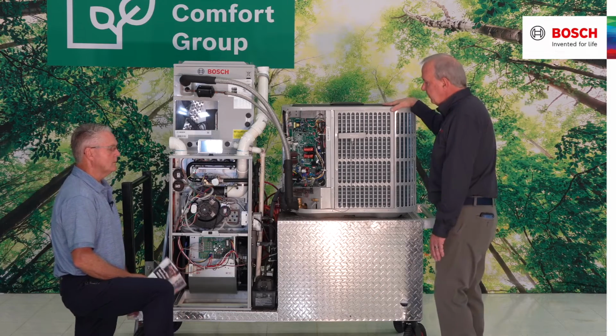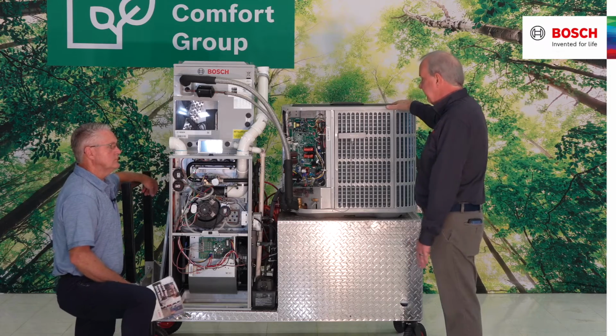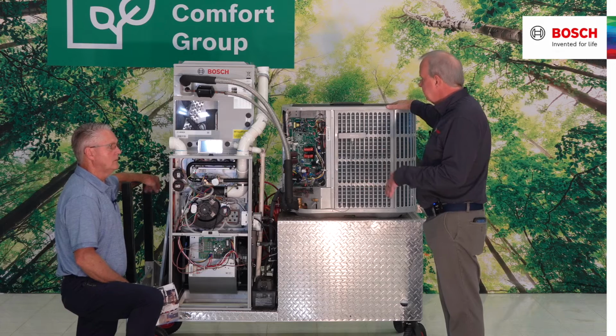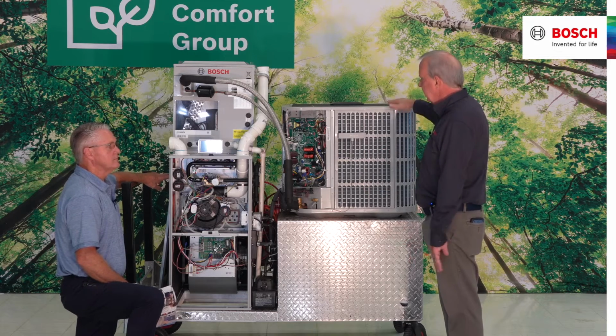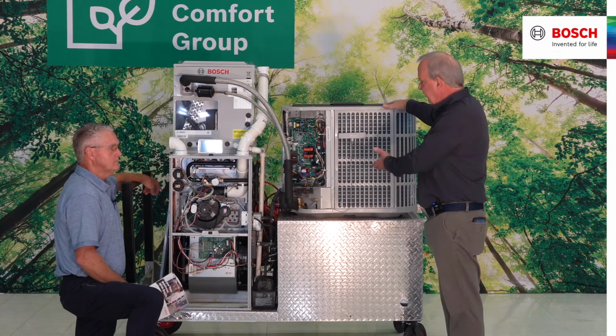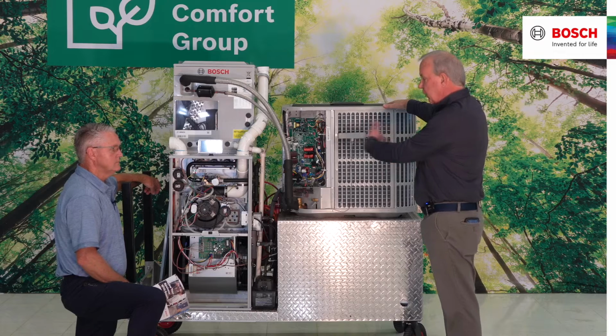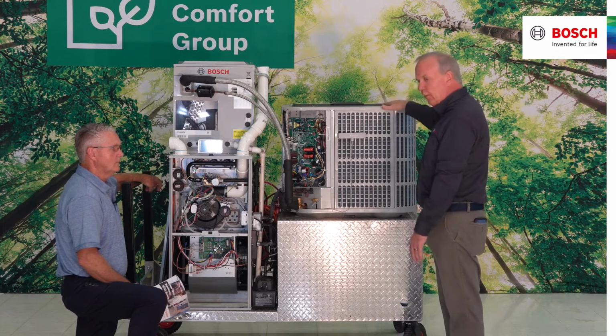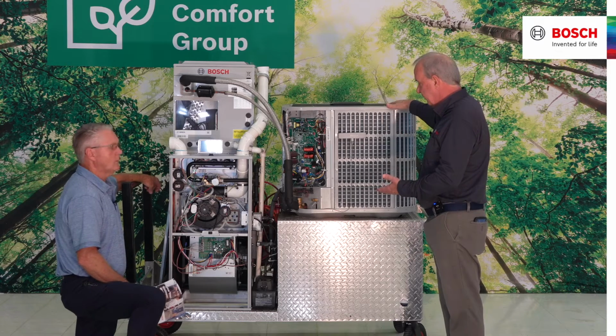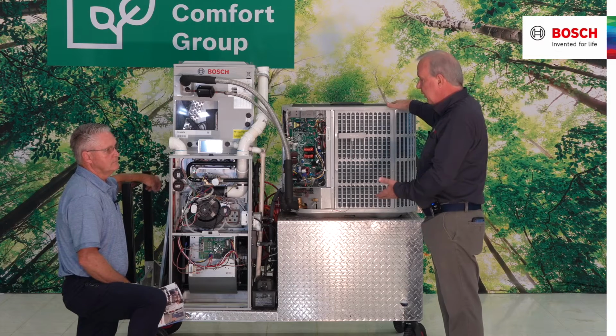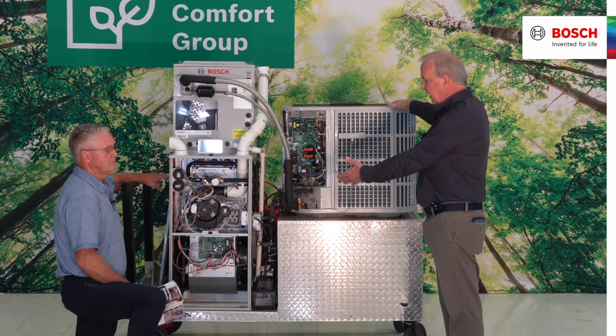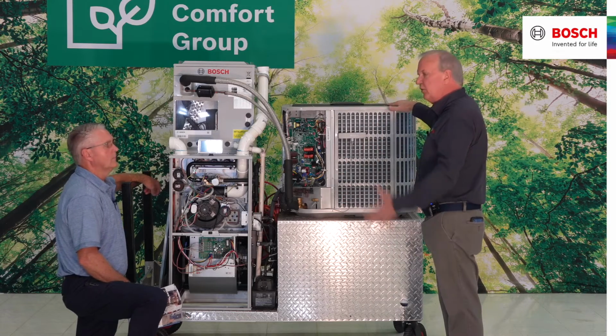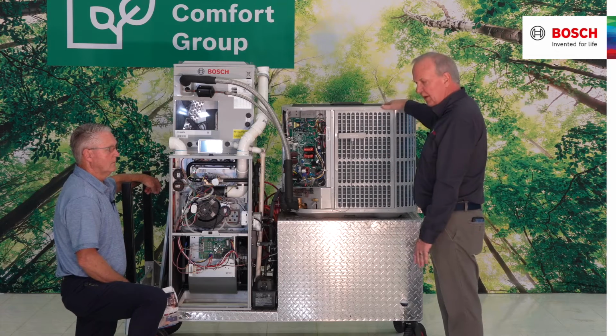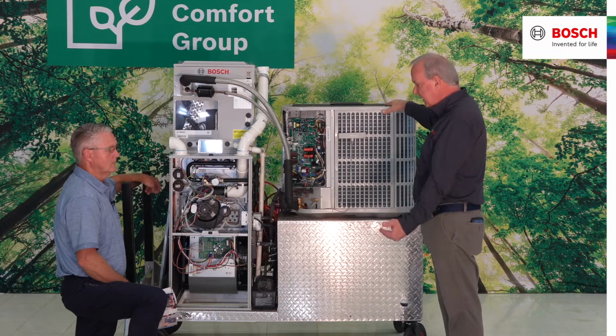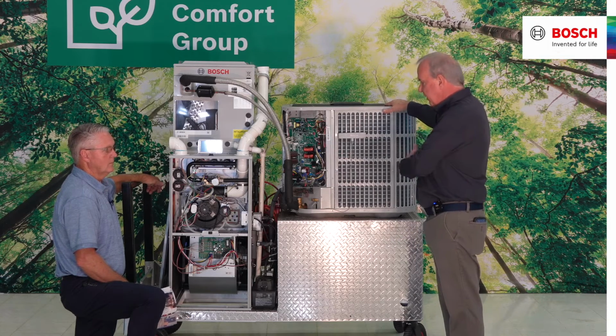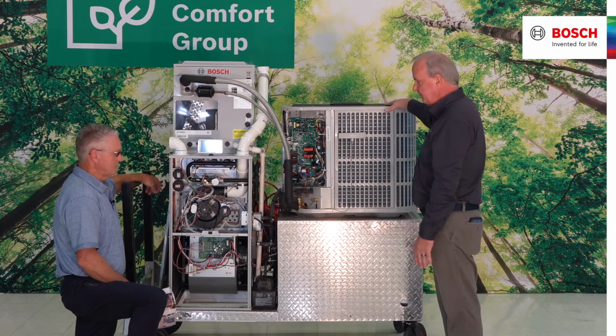So when we're in a heat pump configuration and we do initiate a defrost mode, there are different parameters for what initiates the defrost mode. When we go into the defrost mode, we're putting a 24-volt signal on that white wire coming from the condensing unit going back to the furnace. We know that when we're in the defrost mode, we're actually in the cooling cycle. Right. At that point, we're going to start blowing some cold air. So we send that signal back to our furnace to give us a low fire to temper that air so we don't get that blast of cold air in the house during the defrost cycle. Once the defrost cycle is completed, that 24-volt signal is taken away from the furnace and we go back to normal heat pump operation. Absolutely. Sounds good.